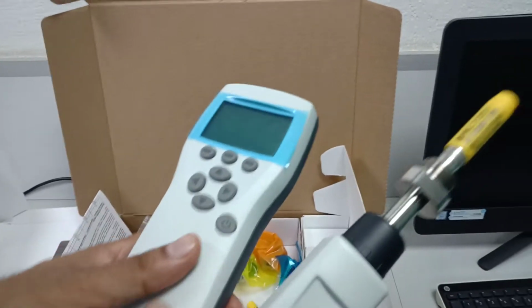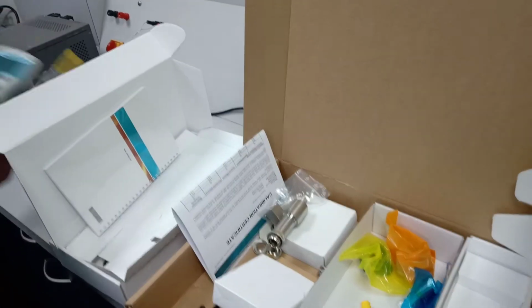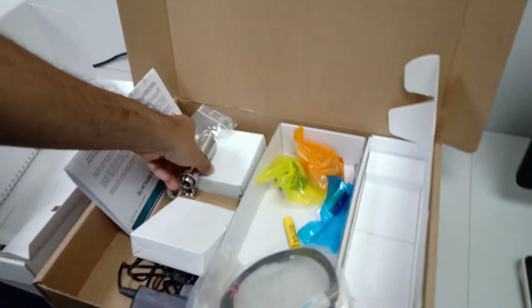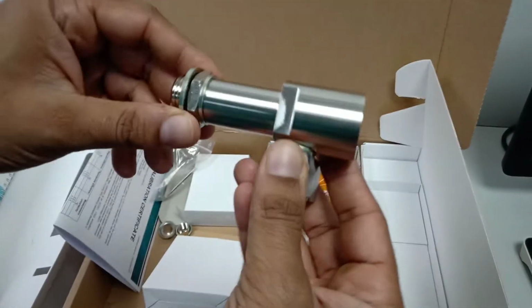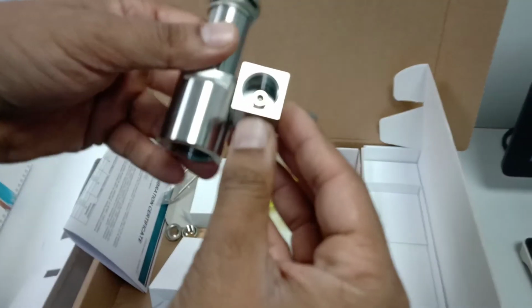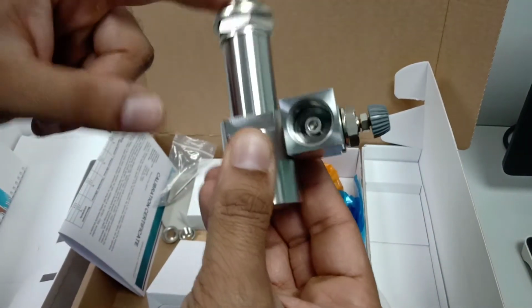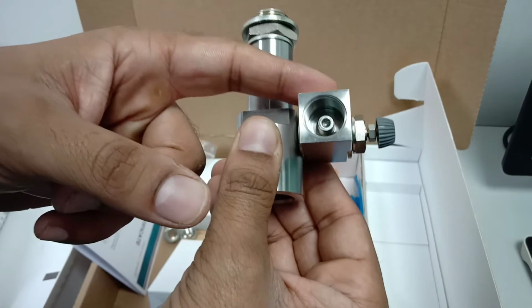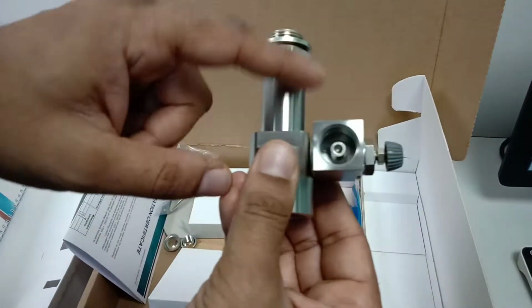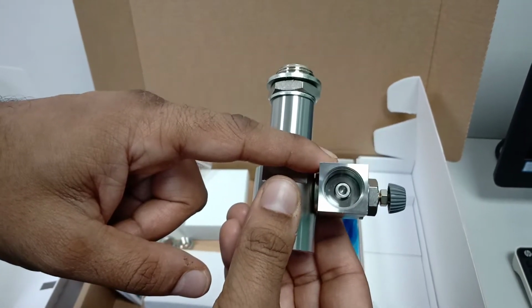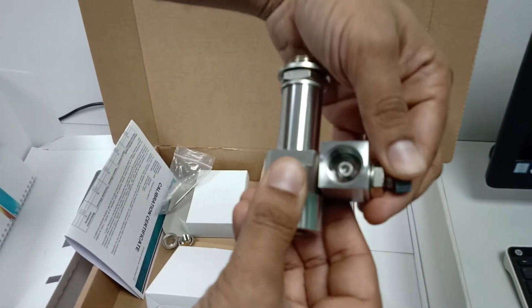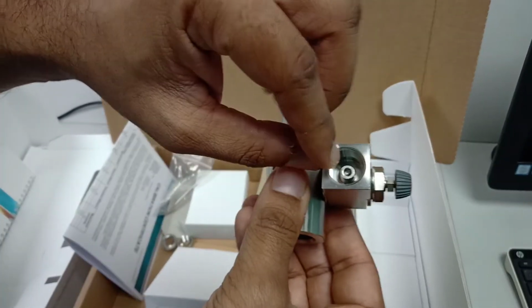SF6 has a molecular mass of 146, so it is quite heavy gas, and we use this special probe for dew point measurement. Along with it comes this two pressure sampling cell. So this is used to measure for SF6 in order to have the minimum leakage of SF6. SF6 is a greenhouse gas, so we have to avoid any leakage in the atmosphere. So this comes with this leak screw. You can adjust for the minimum amount of SF6.